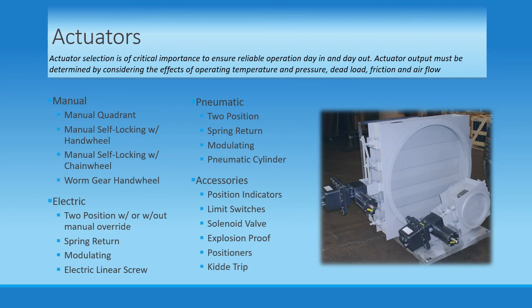Pneumatic actuators use the supply of compressed air to move the damper blades. They are an alternative to electric or manual operators and in many cases are preferred in industrial applications because they supply higher torque at both a lower initial cost and lower maintenance cost over time than electrics. They furthermore tend to have a smaller footprint than equally powerful electrics and do not require a potentially hazardous power supply to operate.